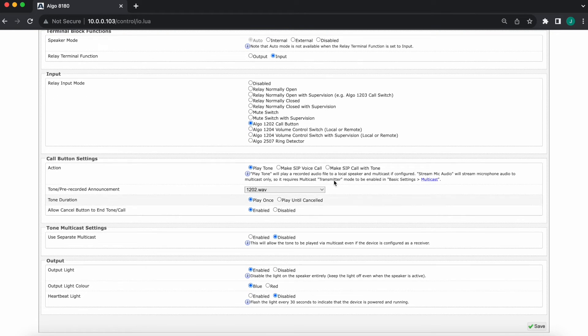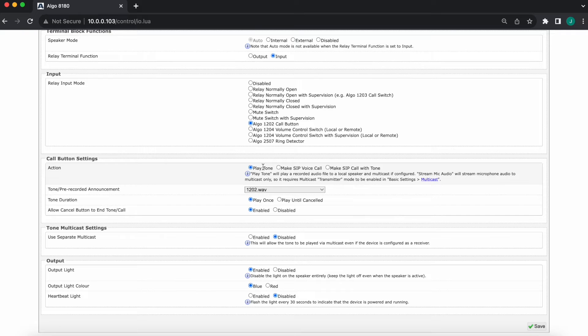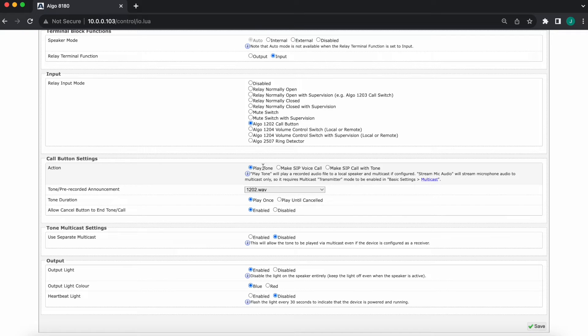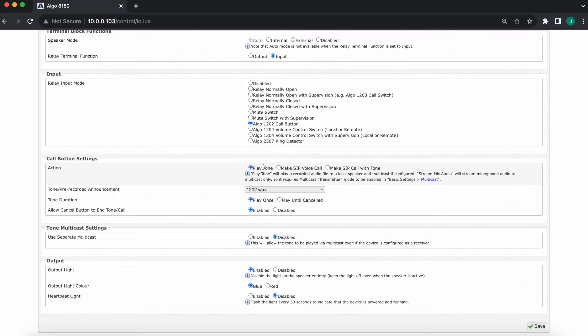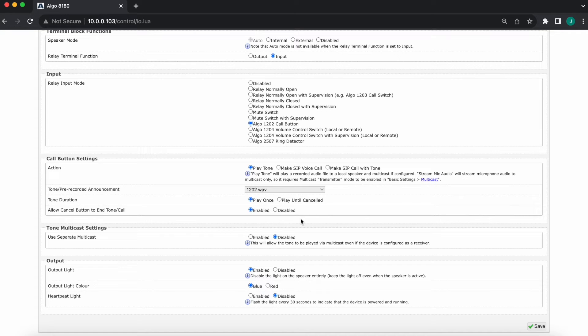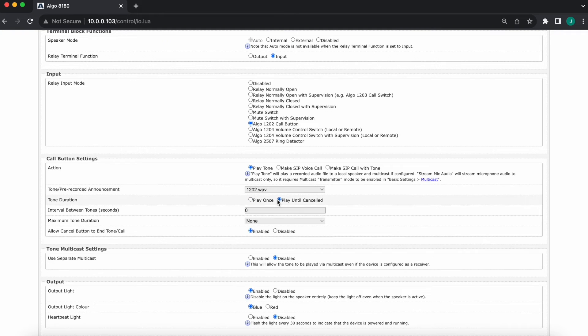Now, we'll talk actions. You have a few actions to select from, and the actions might change a little bit depending on which mode your relay input is set to, but generally, you have a play tone mode. Of course, focusing on speakers. The equivalent to play tone mode would be just fire off a visual pattern on a visual alerter. So play tone will play a local tone on this device. If this happens to be a multicast transmitter, it will transmit the tone to whichever zone you've set it up to. Right now, it's not, so it's just going to be local, and then you can get a few options in configurations that are specific to the play tone action. So is it going to play once? Is it going to play over and over? Can you cancel it? And things of that nature.